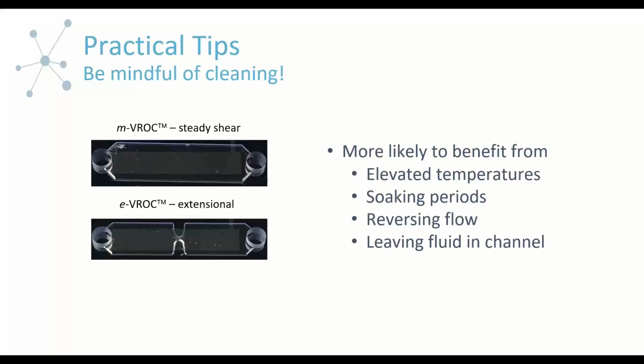And then also for some particular samples, you may never want to dry the channel out. It may be better to have your sample introduced into an already wet channel to prevent additional deposits or film formation that might occur that would be problematic to clean out later. So cleaning is extra important when we're dealing with our extensional chip.